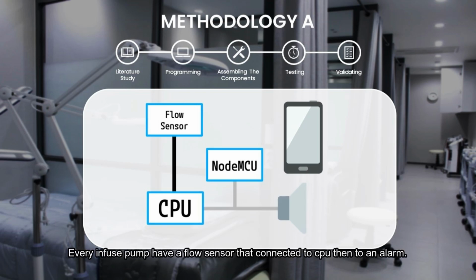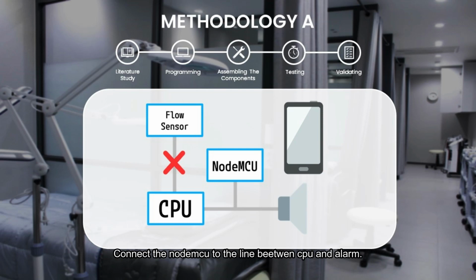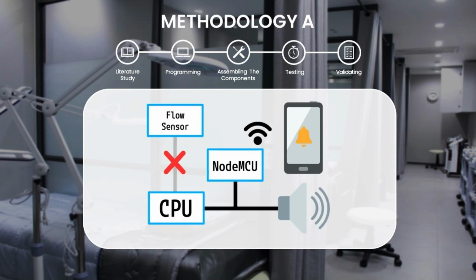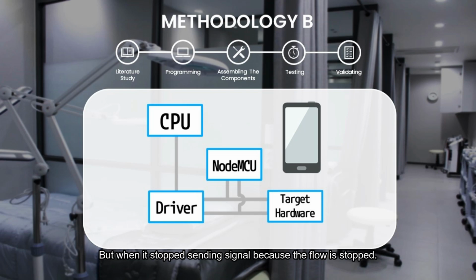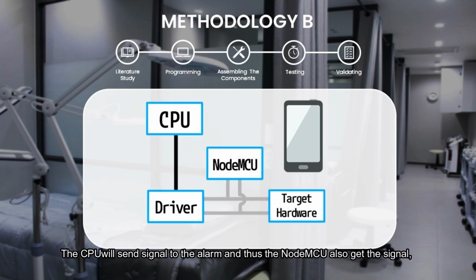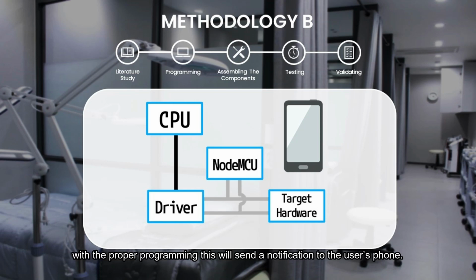Every infusion pump has a flow sensor connected to the CPU and then to an alarm. Connect the NodeMCU to the line between CPU and alarm. When the pump is used, the sensor will send a signal to the CPU. When it stops sending a signal because the flow is stopped, the CPU will send a signal to the alarm and thus the NodeMCU also gets the signal. With the proper programming, this will send a notification to the user's phone.